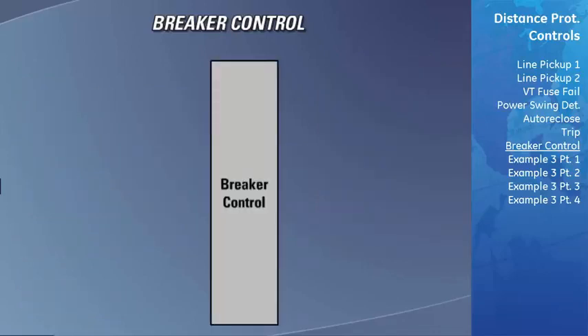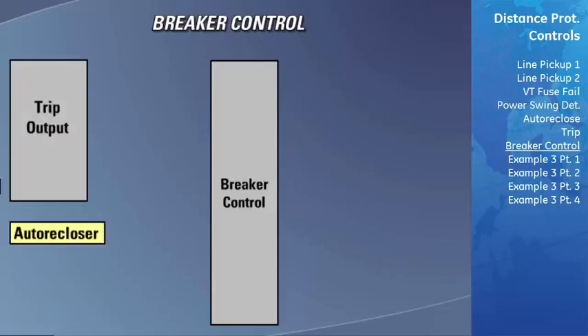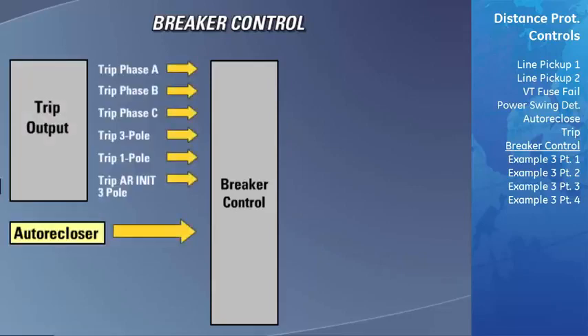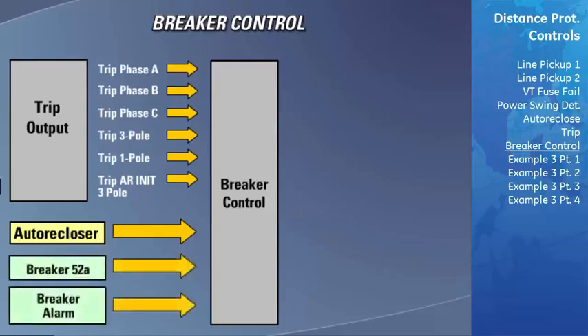Using the breaker control feature, the user now only needs to configure the trip output feature and the auto reclose feature. The outputs of these two elements are internally hardwired to the breaker control feature of the D60. Finally, the user must program into the breaker control scheme which D60 contact inputs are being used to monitor the status of the breaker. The breaker control scheme will take care of the rest of the logic.